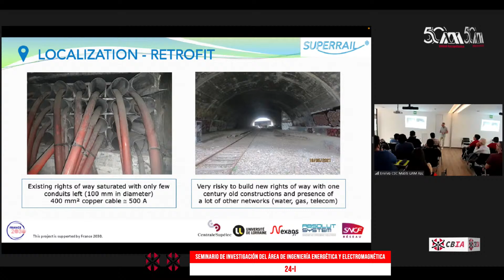On the left side, this is the duct already used by the 400 square millimeter cable. They are almost all filled with cables used for the current for feeding the train. In fact, there are only 2 remaining ducts. With these ducts, and given that one cable can operate at 500 amps in permanent operation, it is not possible to get more power, except if you do a lot of civil engineering on this bridge, which is centuries old and just below the track. So in fact, it was not a good bet to try this solution, and this is why the superconducting project is being built. We will place the cable in the 2 remaining ducts here. So there is no need for civil engineering, just using what we have, and this is sufficient to pass through 1,000 amps to the train.